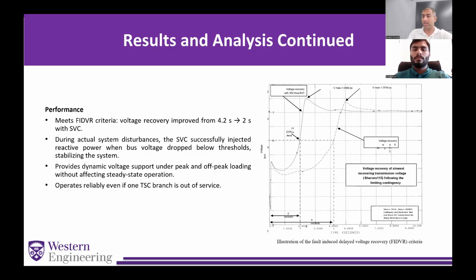In this slide, measured events showed recovery time improving from 4.2 seconds to 2 seconds at the slowest bus, meeting FIDVR compliance while keeping peak voltages in check. During real disturbances, the SVC fired exactly when thresholds were crossed, stabilizing the corridor under both peak and off-peak loading. That predictable behavior reduced the need for UVLS and cut the risk of motor stalling spirals.